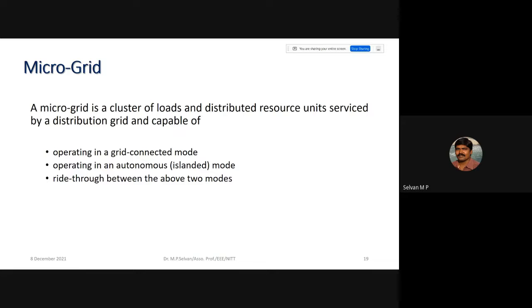A group of distributed sources means not just one inverter - there will be multiple inverters fed by renewable sources, and they should coordinate with each other. One inverter should form the grid, and the others should follow it. So who will form the grid locally when the main grid is not available? There should be decision making and control involved in that. If that facility or feature is available, then we can call it a microgrid. It should work in an islanded mode.